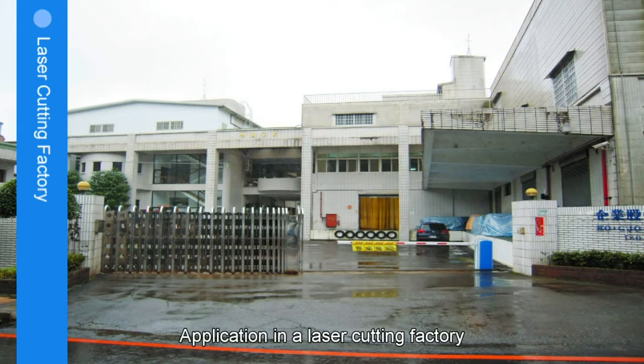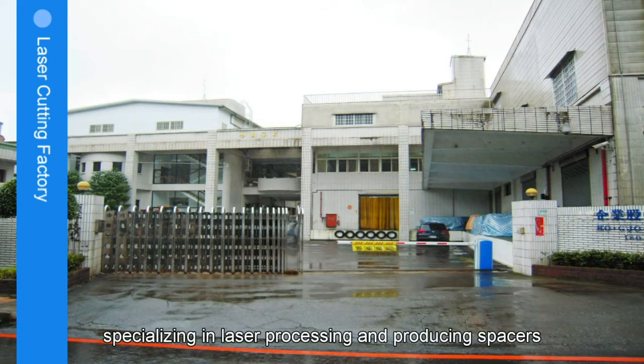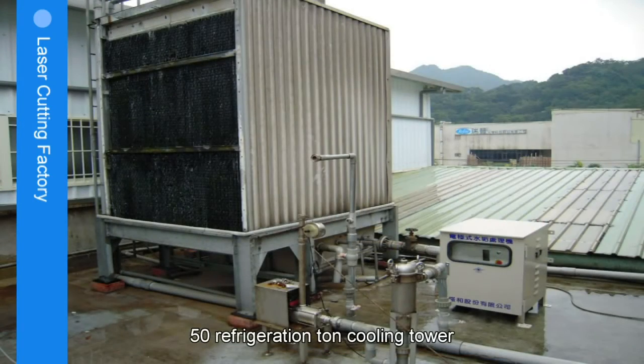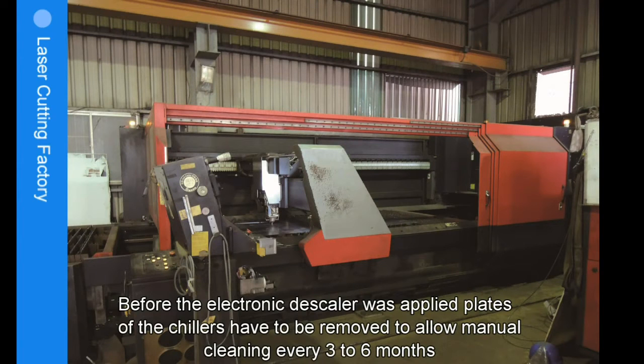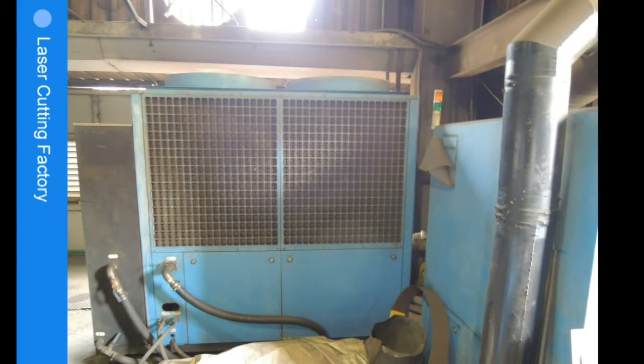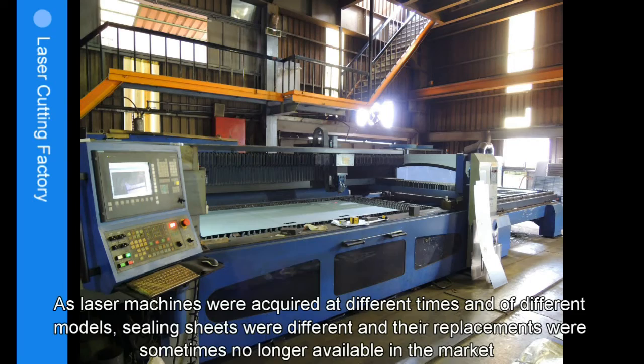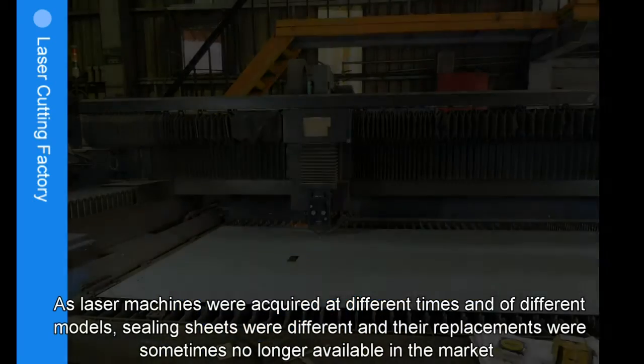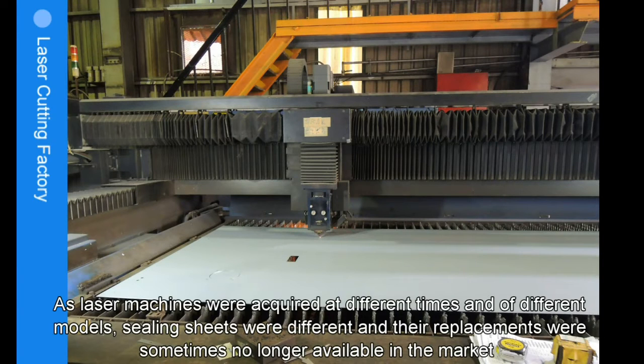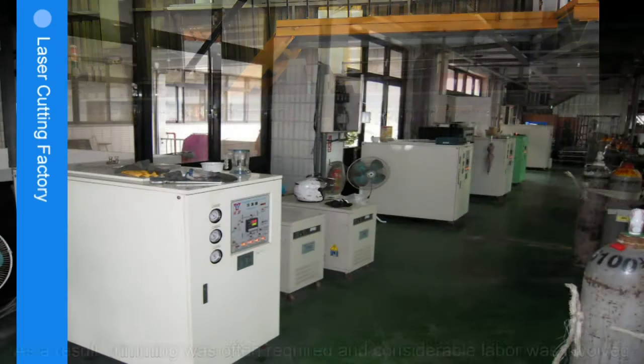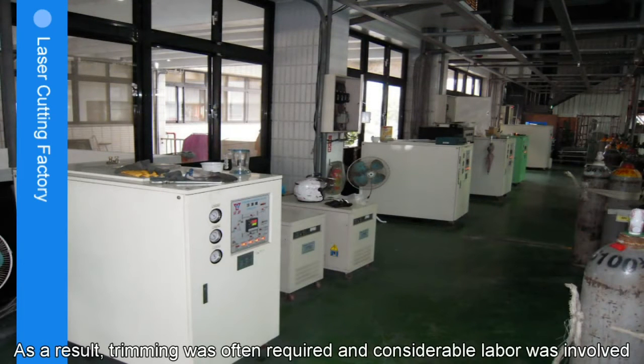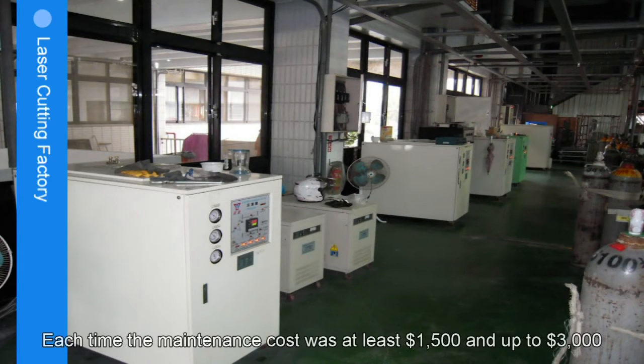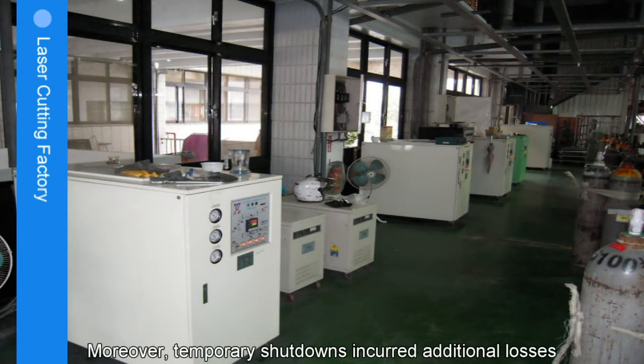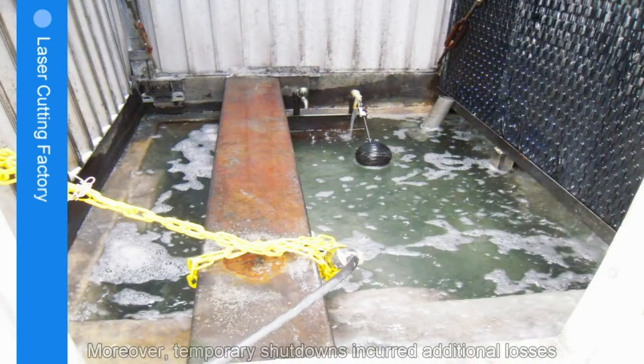Application in a laser cutting factory, specializing in laser processing and producing spacers. 50 refrigeration ton cooling tower. Before the electronic descaler was applied, plates of the chillers had to be removed to allow manual cleaning every 3 to 6 months. As laser machines were acquired at different times and of different models, sealing sheets were different, and their replacements were sometimes no longer available in the market. As a result, trimming was often required and considerable labor was involved. Each time the maintenance cost was at least $1,500 and up to $3,000. Moreover, temporary shutdowns incurred additional losses.